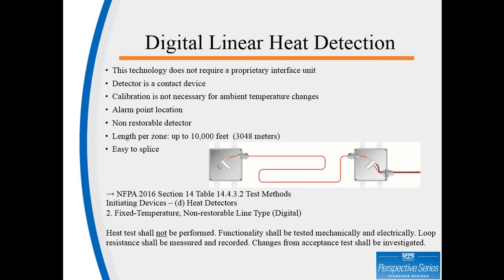Digital linear heat detection. This technology does not require a proprietary interface unit. The detector is a contact device, as a matter of fact is listed as an open contact device. Calibration is not necessary for ambient temperature changes. Alarm point location is available. Non-restorable detector. Length per zone up to 10,000 feet, 3,048 meters. It's easy to splice. Maintenance and testing is very simple, as provided and required by NFPA 72, 2016, Section 14.